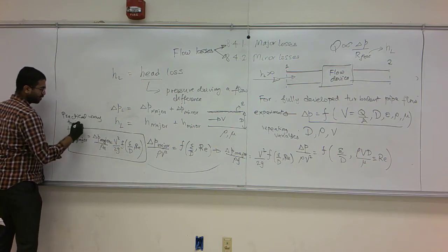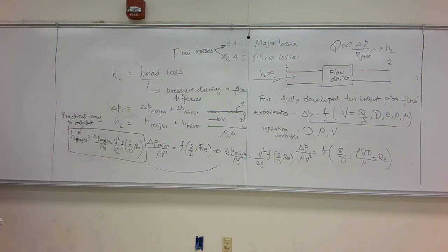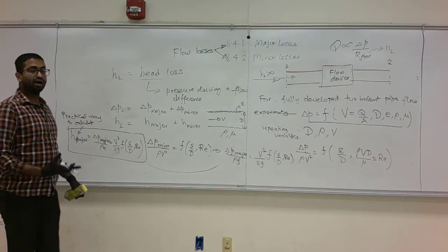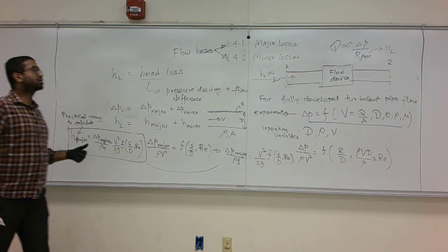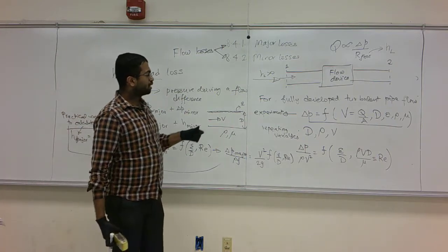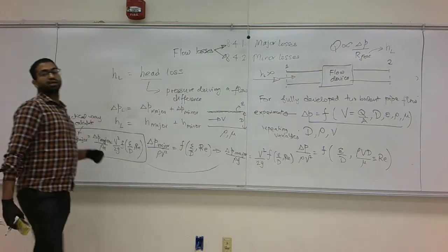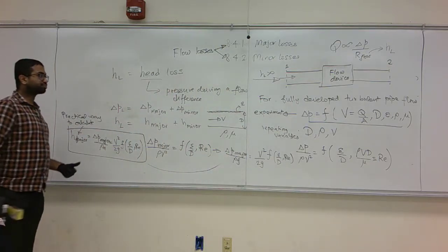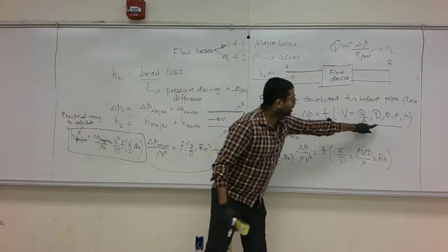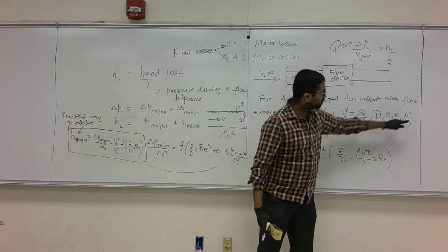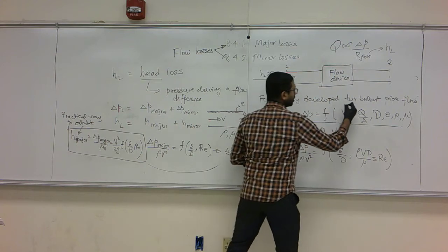to calculate H major when you have experimental data available, and there is a lot of experimental data available. As engineers, we have at our disposal a lot of different types of measurements that tabulate the flow losses, so that when you are doing fluid design, your goal is, given these are my flow parameters, velocity, diameter, roughness, density, viscosity, what is my pressure loss? Given these, what is this?